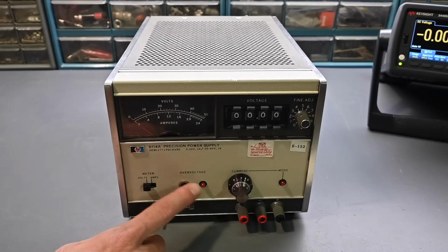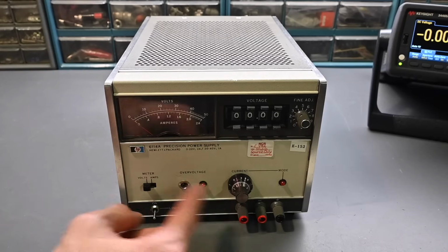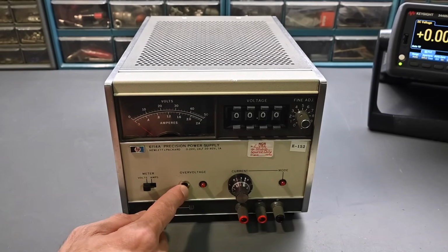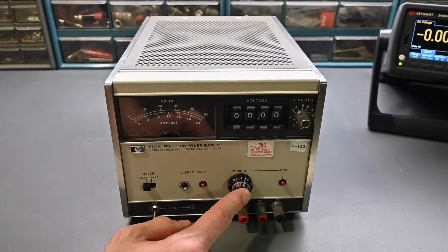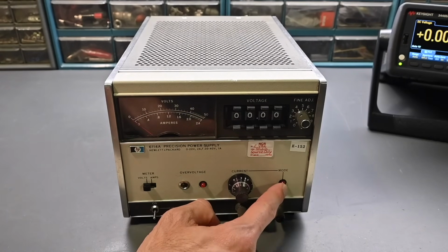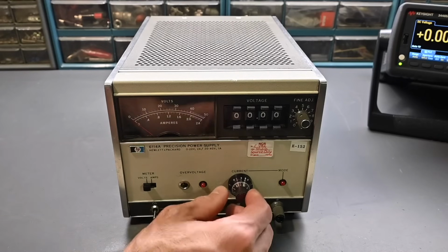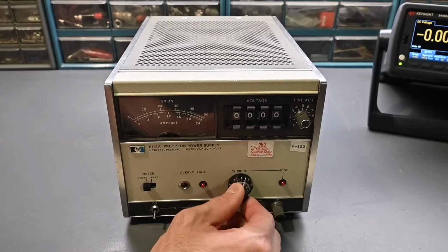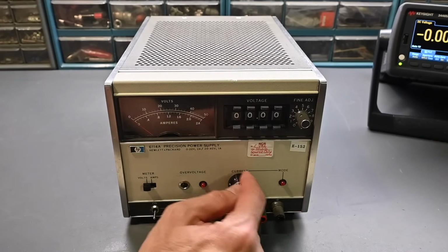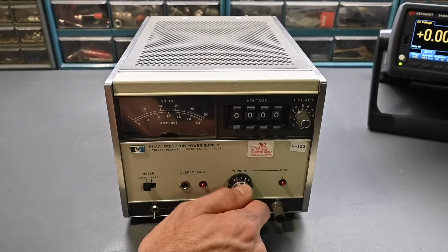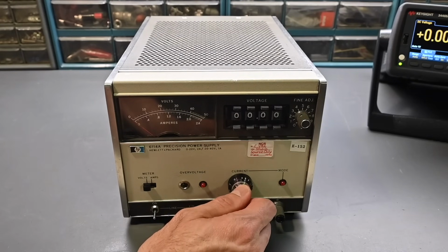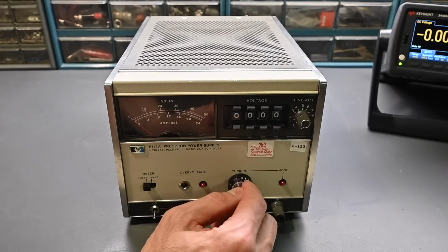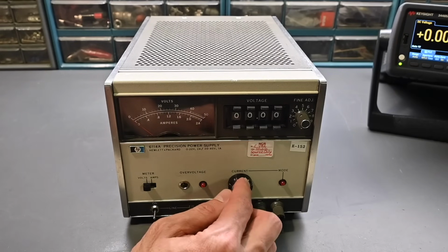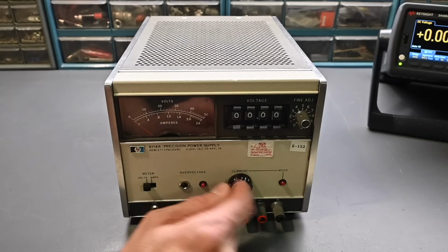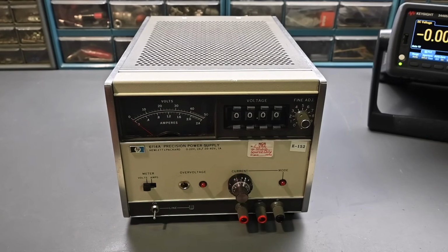Now right here, for overvoltage, this LED comes on if it does go into overvoltage, and there's a setting right here. Current adjustment for constant current mode, and if it's in constant current mode, that LED turns on. Now the numbers on this dial right here, this is a multi-turn dial, so you can see the outer ring counts the number of turns. It goes all the way up to the maximum right there. The dial doesn't seem to be related to the actual current value, so the numbers on here don't mean anything, they're just an arbitrary value.